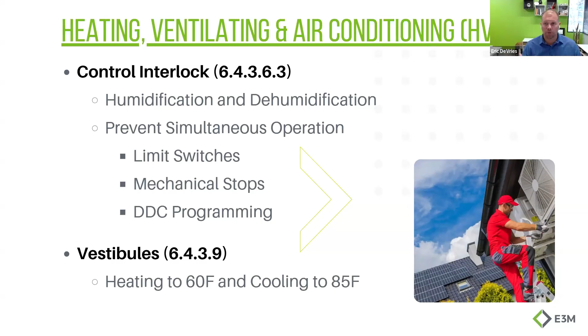Another change, not all that pertinent to Michigan, but I want to bring it up in here for those that may work out of state. The last energy code, we could not actively heat a vestibule above 60 degrees. They're trying to make that a transitional space, not just part of outside or part of the building that's open outside. You can now not actively cool that below 85. Not a big issue here in Michigan. I can tell you I've been to Phoenix last summer and walked through a vestibule that was probably 130, 140 degrees because the cooling wasn't working. That's where they're trying to use some of that to manage that. So just be aware there.